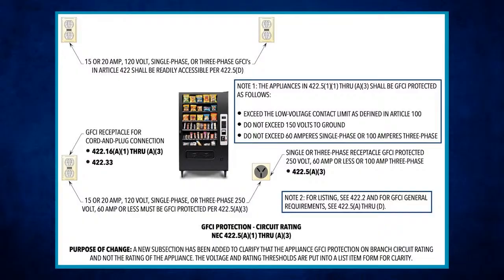So if I look at 422.5(B), that's your typing location, let's see what it says. It says the GFCI shall be readily accessible, listed, and located in one or more of the following locations. They tell you one or more, but I want to go back before that, because the last sentence in 422.5(A) says multiple Class A protective devices shall be permitted, but shall not be required.